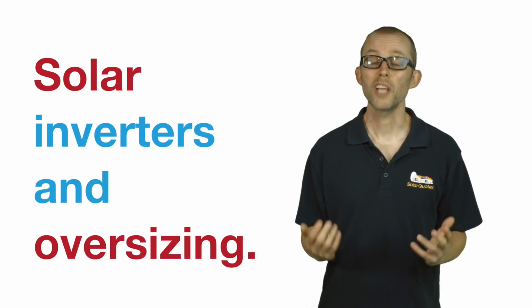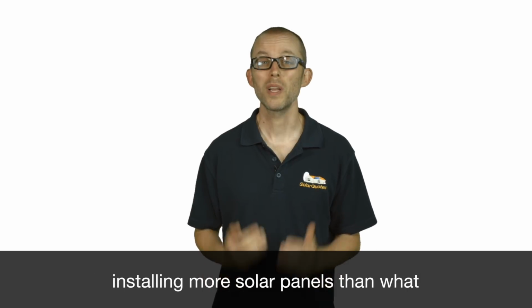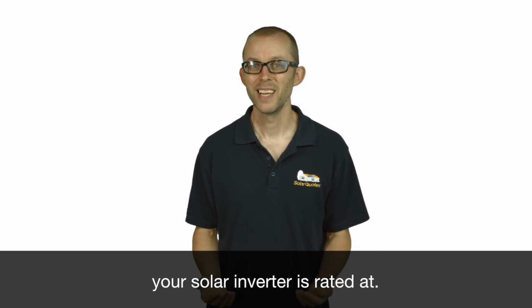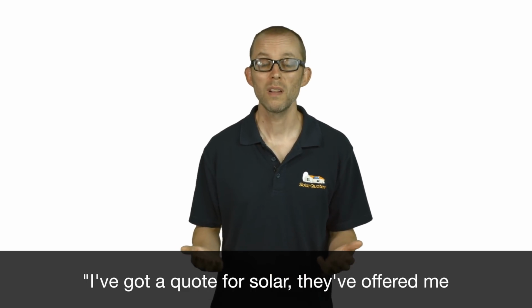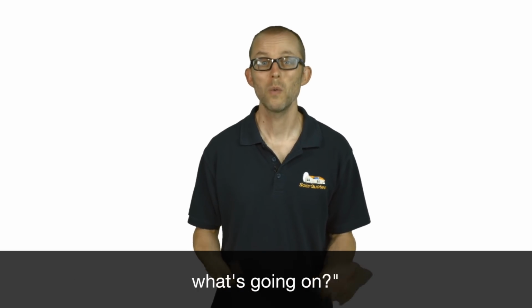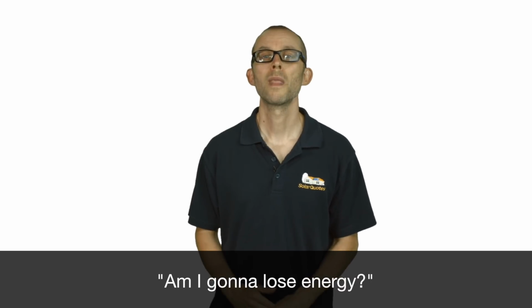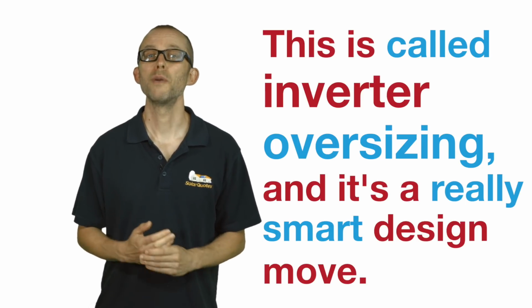Solar inverters and oversizing. When I talk about oversizing, I'm talking about installing more solar panels than what your solar inverter is rated at. Now, I get emails all the time saying, I've got a quote for solar, they've offered me a 5 kilowatt inverter and 6.6 kilowatts of panels. What's going on? Am I going to blow up the inverter? Am I going to lose energy? This is called inverter oversizing, and it's a really smart design move.